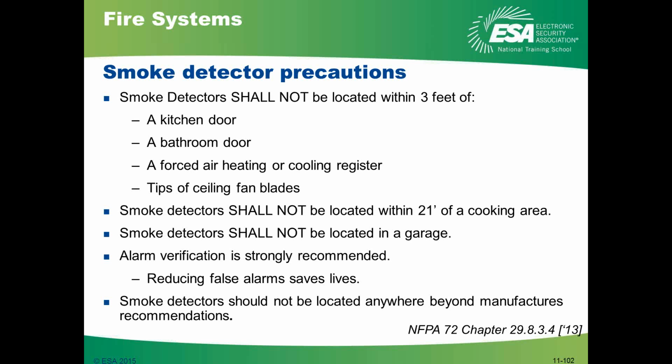We talk about where they shall not be located. One of the interesting things here is that fourth one is, since they're now required, and this applies to smoke alarms and detectors, that we're required to stay 36 inches away from the tip of the ceiling blade in the bedroom, which is a very interesting aspect.